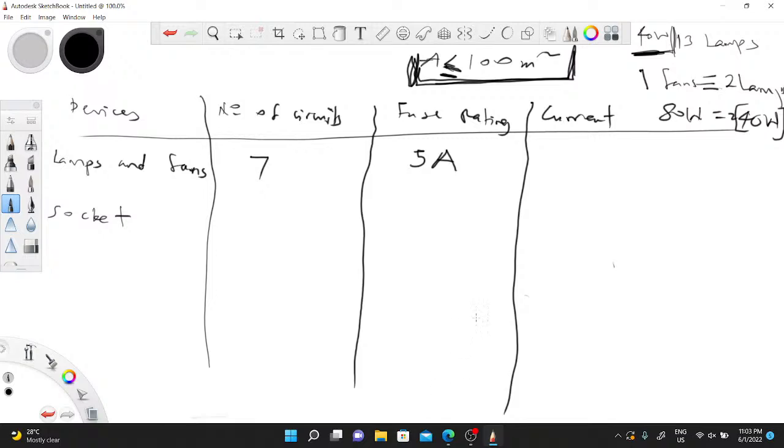If you check the dimensions, you can divide this into 4 quadrants of areas less than 100 square meters. If you check the master bedroom and the living and dining room and multiply the area, you get an area less than 100 square meters. So I can have 4 quadrants, which means I can form 4 circuits.